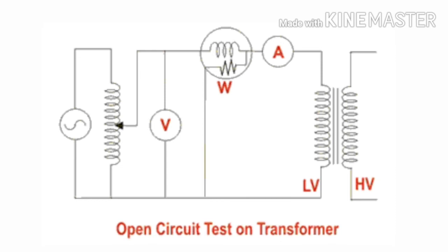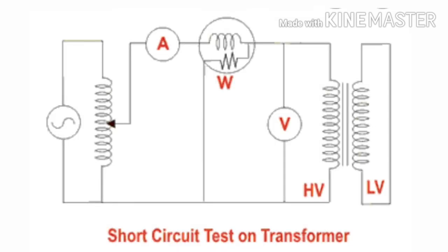So we have to install all the instruments on the low voltage side of the transformer, because the open circuit test is always done on the low voltage side and the short circuit test is done on the high voltage side. In the short circuit test we can measure copper loss. Here the wattmeter reading will give us the copper loss, and the wattmeter, ammeter and voltmeter we have to install on the high voltage side, and we keep the low voltage side short circuited, because the short circuit test is always done on the high voltage side of a transformer.